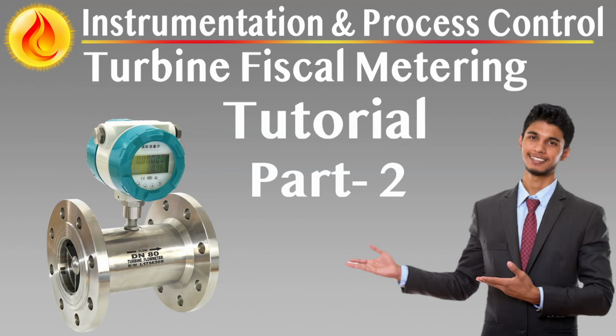Microcomputer-based monitoring and control system: centralized intelligence for measurement, proving, and validation, with distributed control through modular microcomputers. The turbine fiscal metering system is governed by a network of dedicated microcomputers, each assigned a distinct role: stream monitoring, station aggregation, and prover automation. These processors reside in the central control room (CCR), local control room (LCR), or nearby equipment shelter, and serve as the digital core of the metering infrastructure. Their design is modular to ensure that individual failures do not compromise overall system performance.